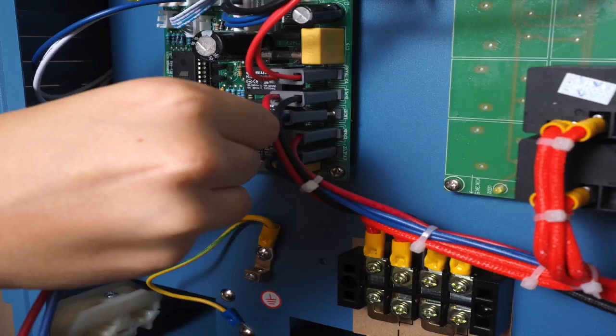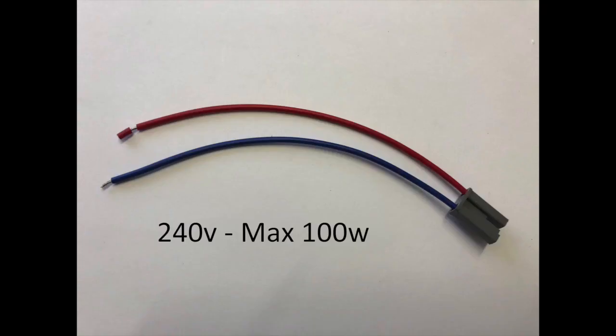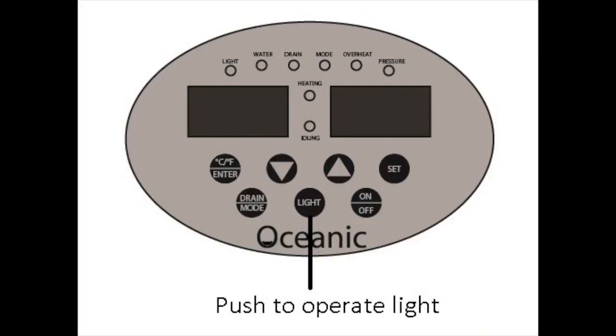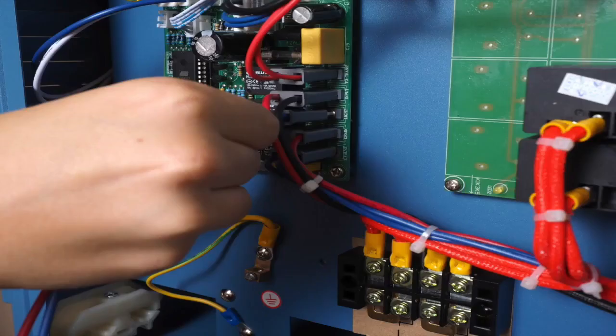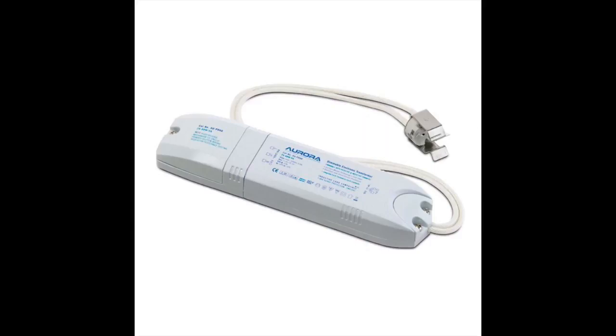There is a connection on the circuit board which gives a 240 volt 100 watt power supply for a light. This can be switched on using the keypad. There is a grey connector supplied in one of the boxes. Plug this into the circuit board as shown. The connection closest to the edge of the board is the neutral. The light in the steam room must be 12 volts so an appropriate transformer should be used.